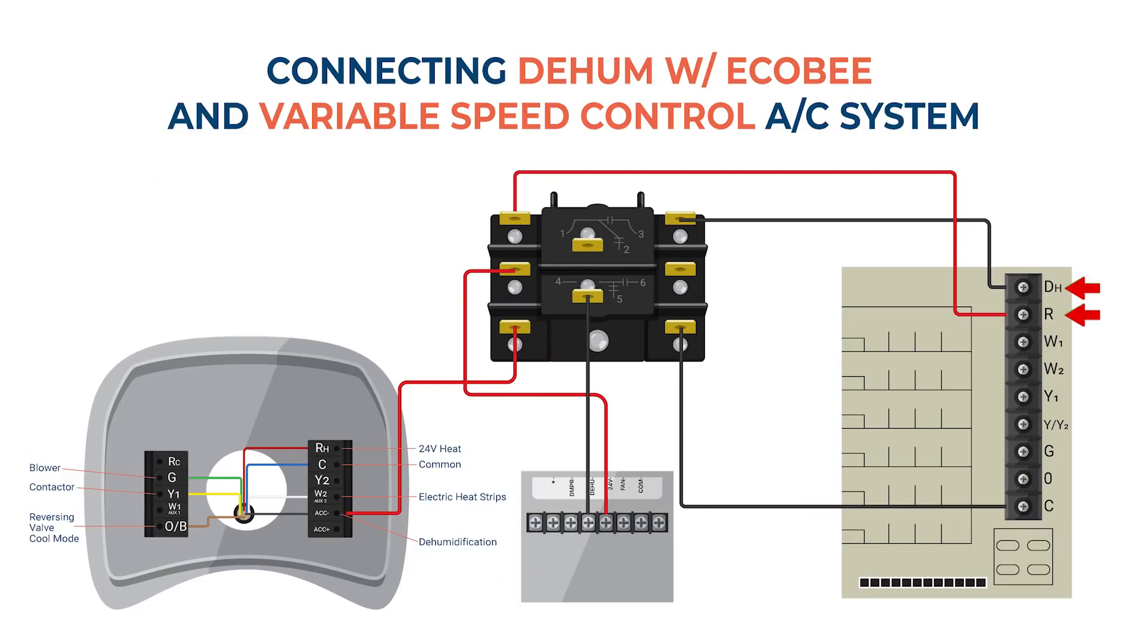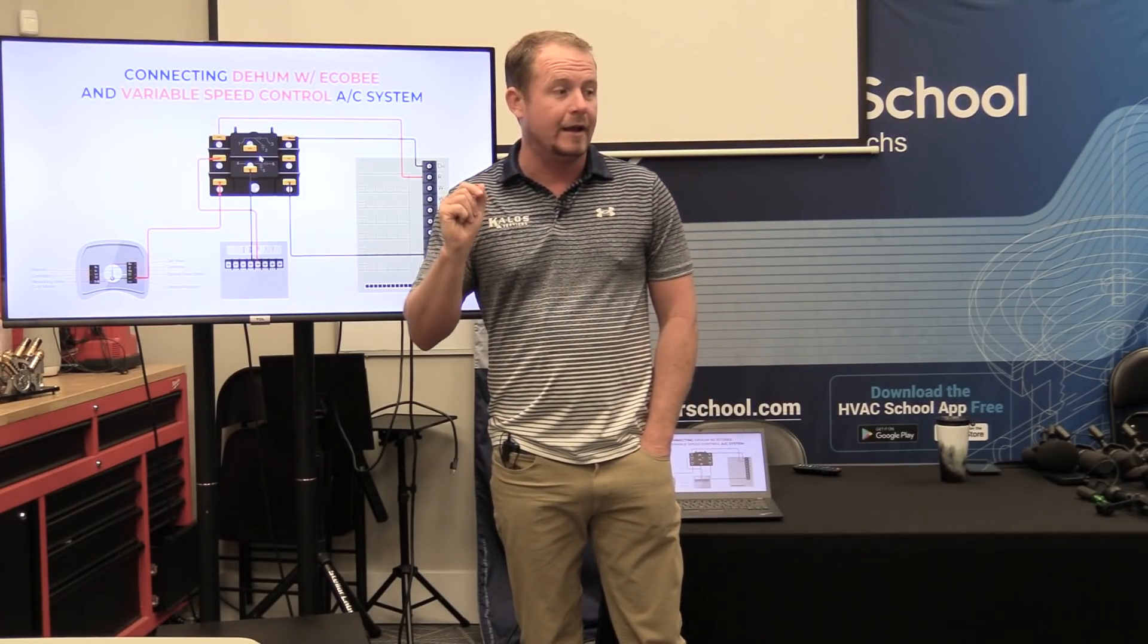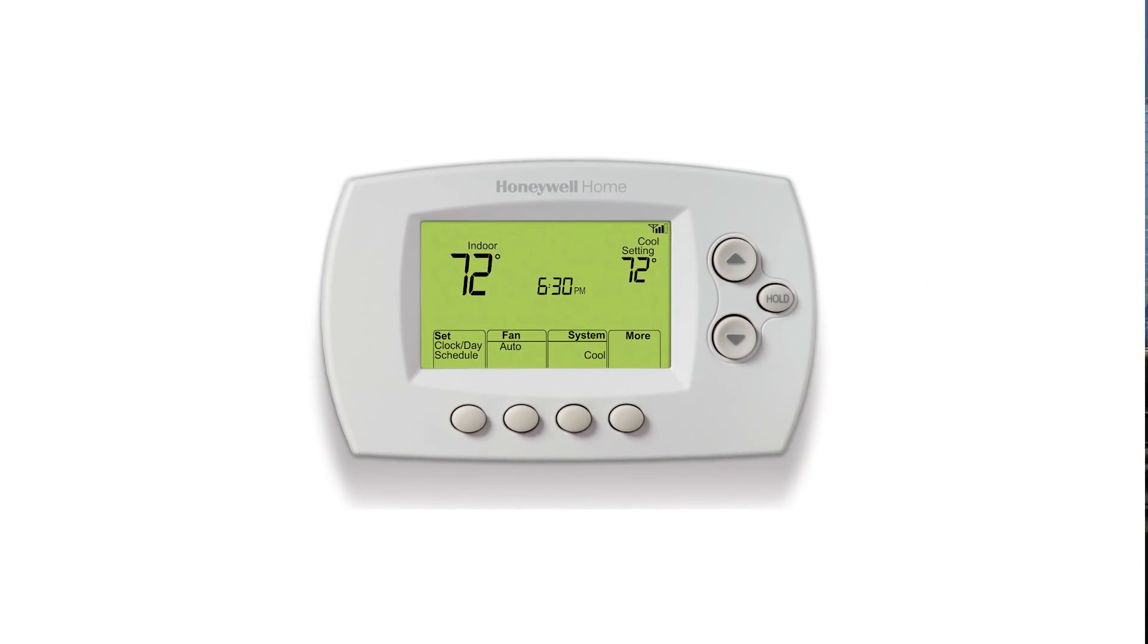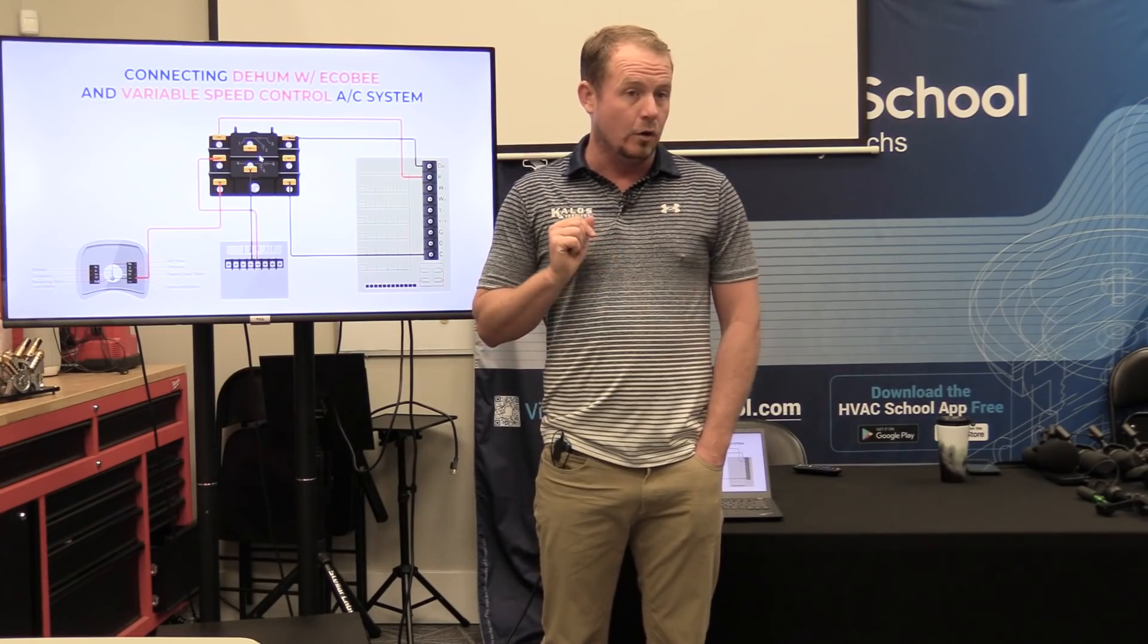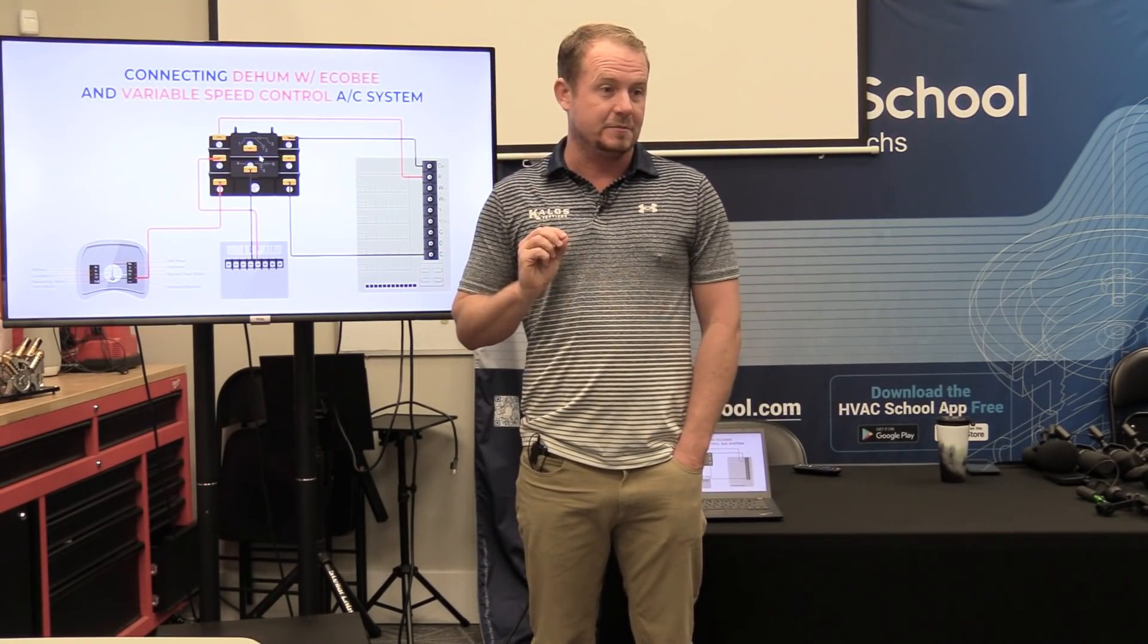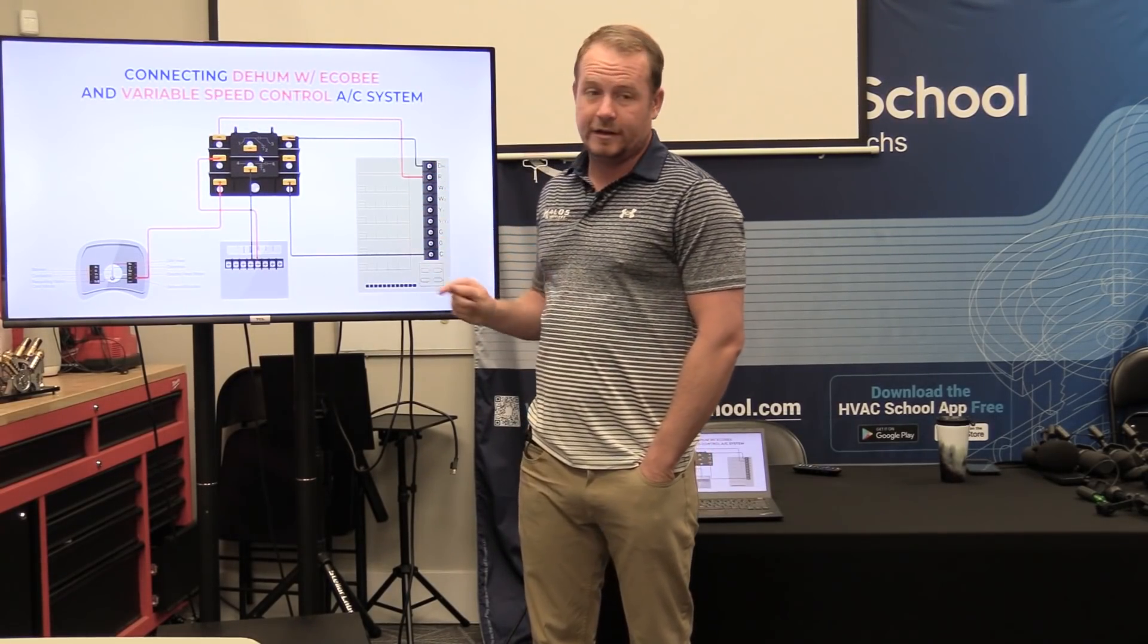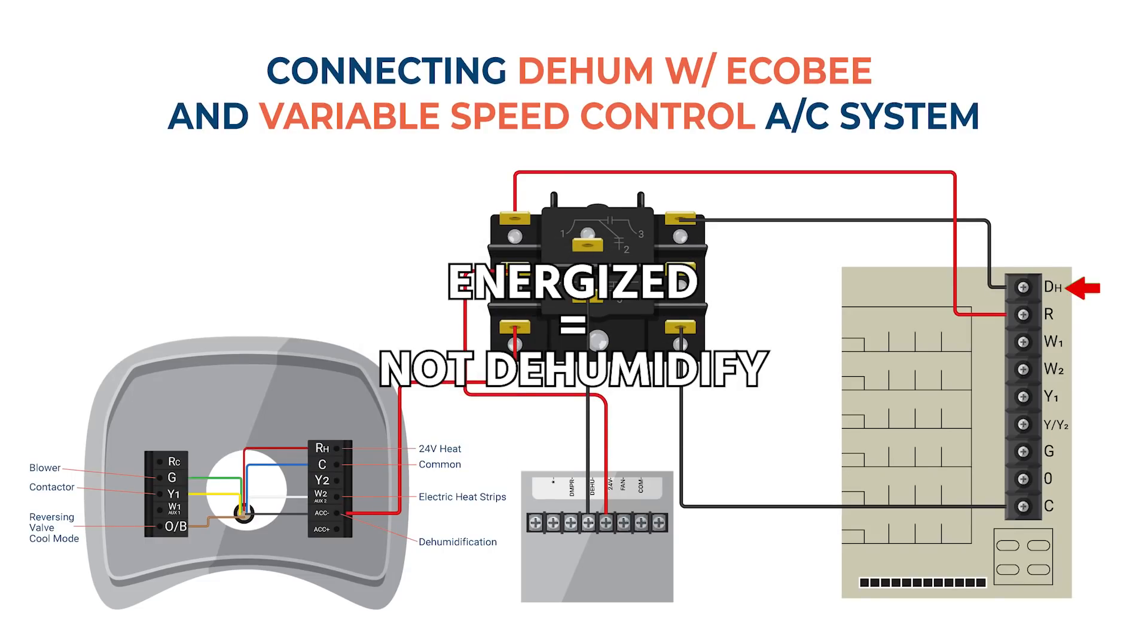If we didn't have an ecobee at all or a Nest, any sort of thermostat that can control humidity, what would we have set up on this board? Jumper wire. We have a jumper wire between DH and R. And what would that do? It removes dehumidification by energizing DH all the time. If DH is energized all the time, then the blower always runs at full speed. Quick note: if you ever replace a thermostat that has a dehumidification mode with one that does not, you need to make sure that you put that jumper back between DH and R. So DH energized all the time equals not dehumidify.